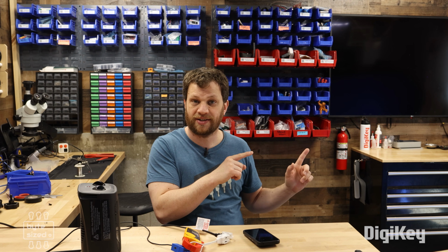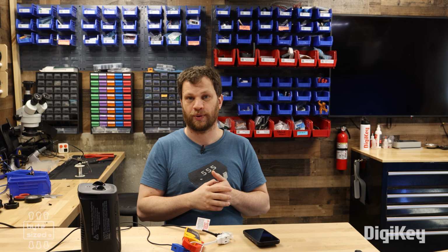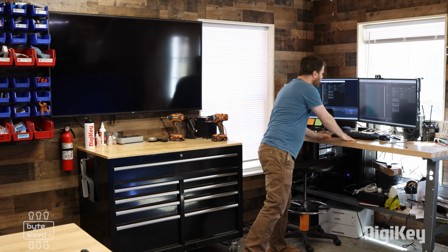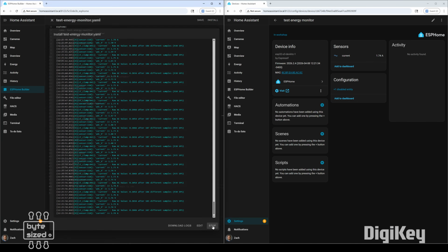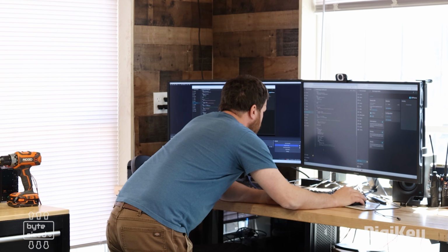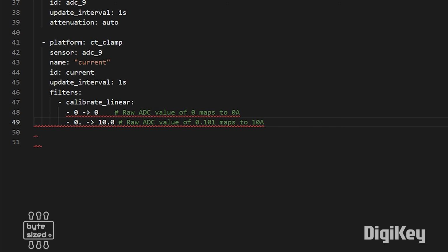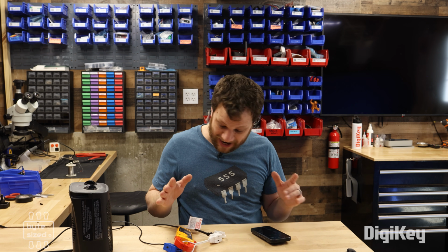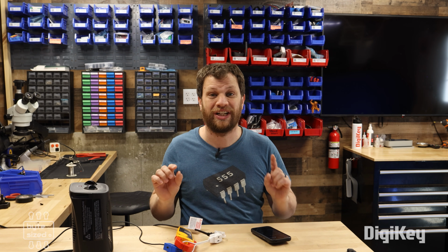Let's go check the logs and see what the raw ADC value is - I'm getting a raw value of about 0.102. Let's close this and change the linear calibration. Instead of 0.6 mapping to 10 amps, we're going to do 0.101. That update went live and now the readings are really close.